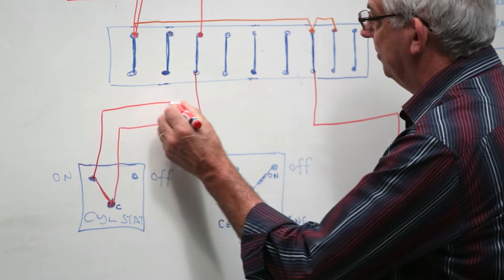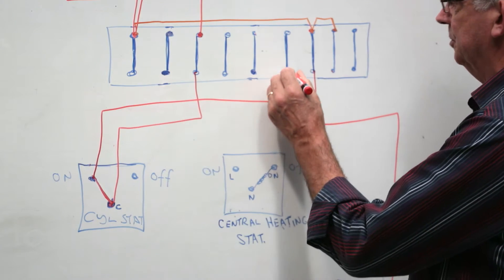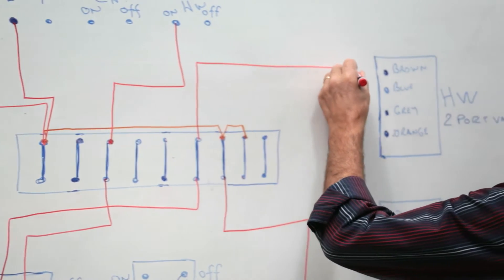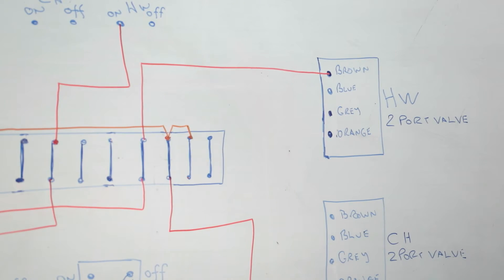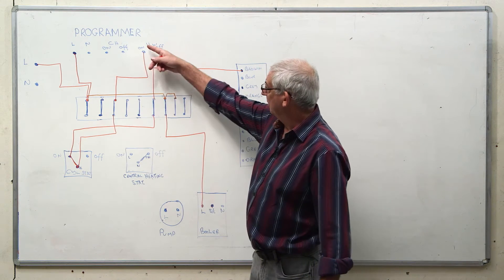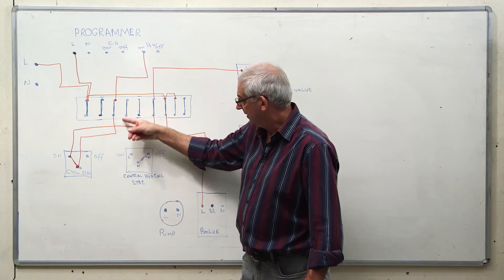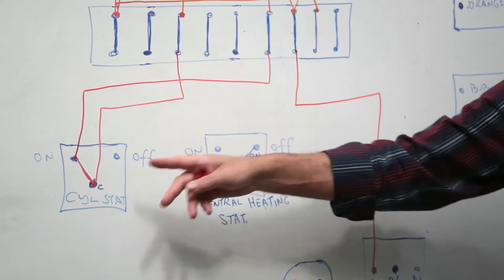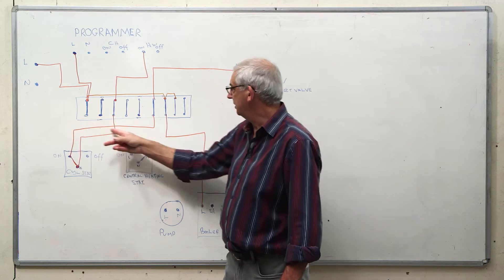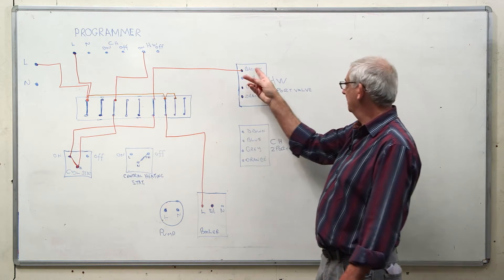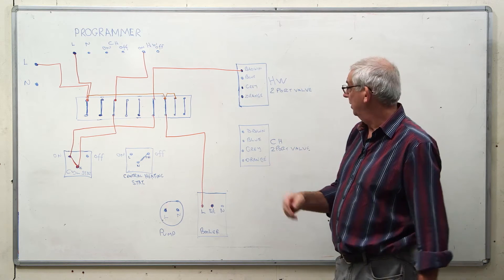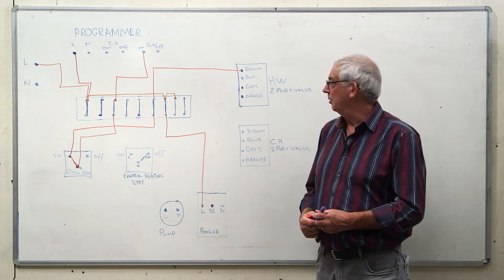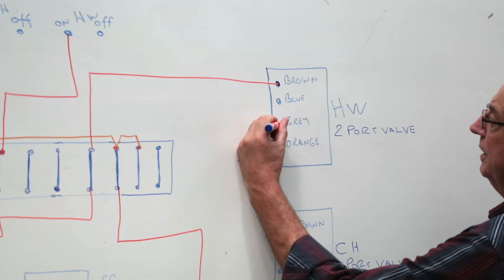When the on terminal's live we need to send the signal to the hot water valve, connect it to the brown. So now we can see programmer's calling for heat. The current flows through to the cylinder stat. The cylinder stat is in the on position. These two are closed. It sends a signal back up through to the hot water two port valve. The two port valve now opens and it makes the micro switch within the valve.